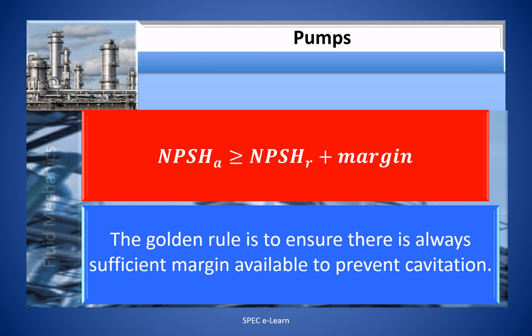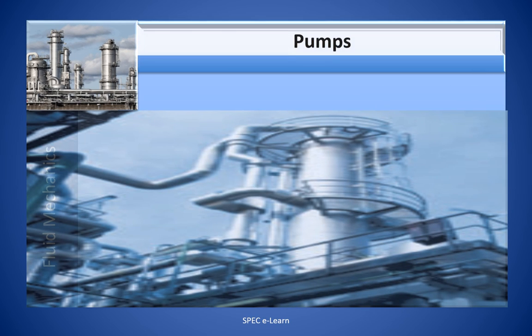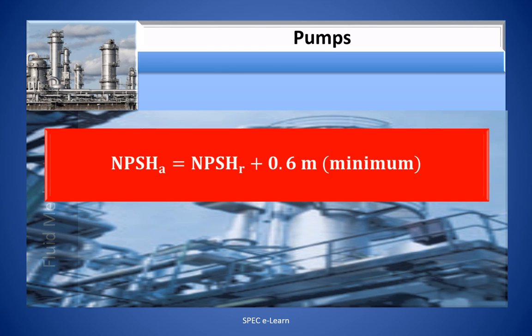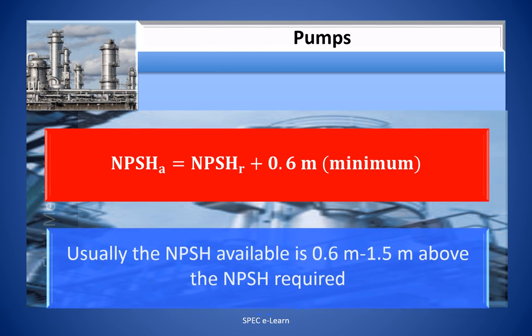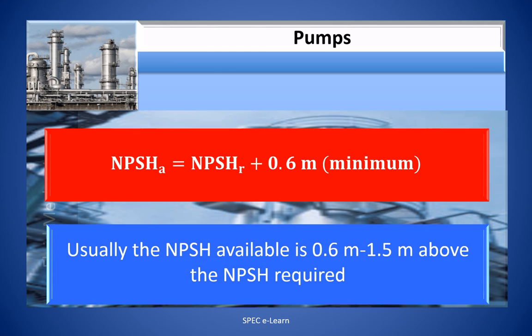Hence, NPSH available must be greater than or equal to NPSH required plus a certain margin. The golden rule is to ensure there is always sufficient margin available to prevent cavitation. The usual design practice is to ensure the NPSH available is 0.6 meters to 1.5 meters above the NPSH required.